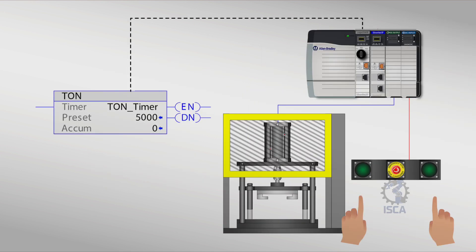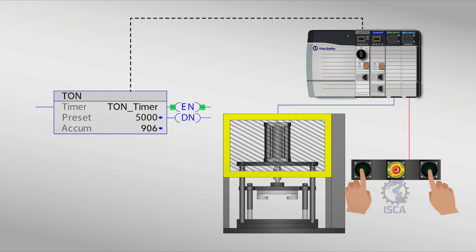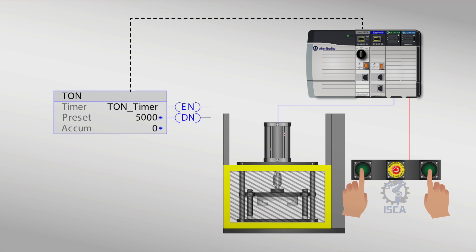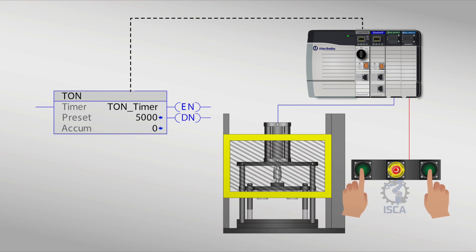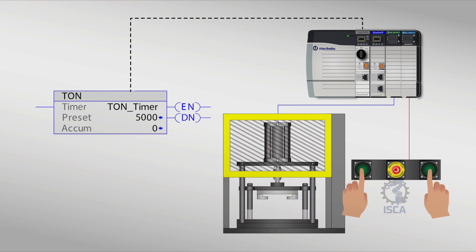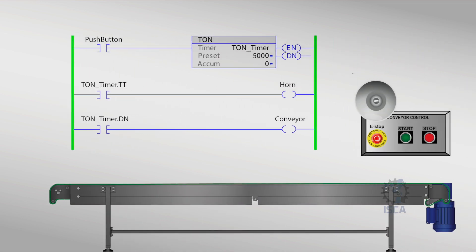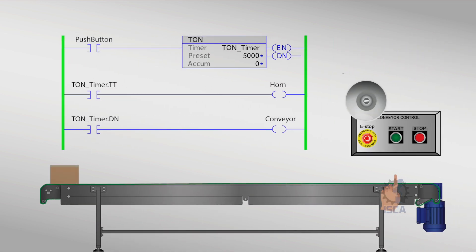The TON timer is the most commonly used timer on automated machines. It is a programming instruction used to delay an application or process for a certain amount of time. When the rung condition is set to true, the timer starts timing. The timer will keep timing as long as the input signal is high or true. The timer instruction will be executed when the input turns on and activate the mechanism after the set delay.